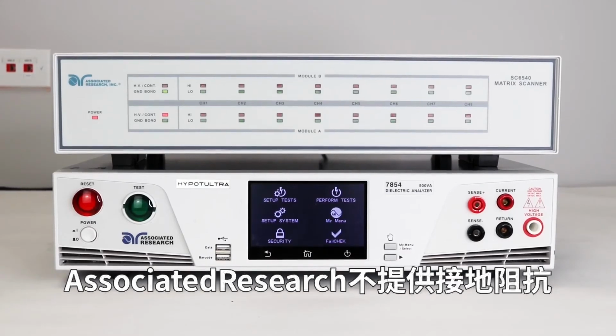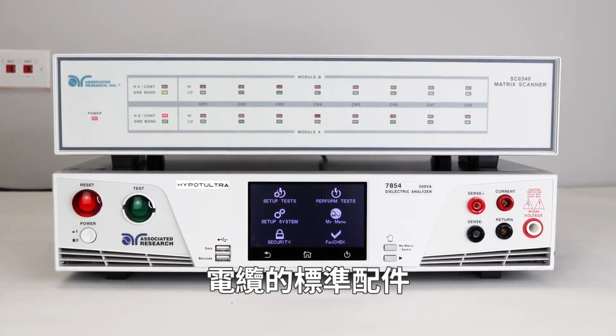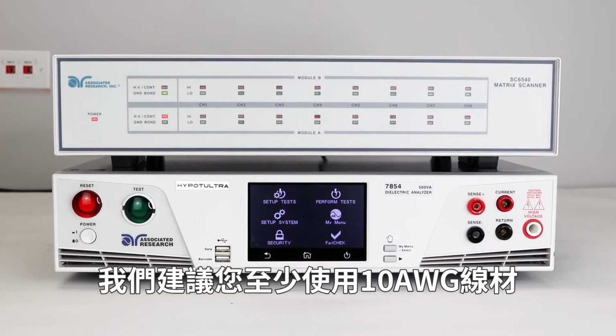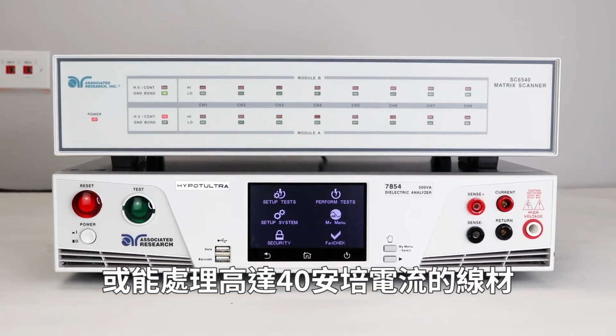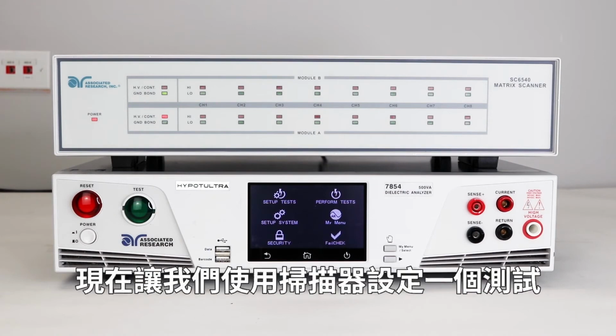Associated Research does not provide standard accessories for the ground bond channels. We recommend you use at least a 10 gauge wire or something that can handle up to 40 amps of current. Now, let's set up a test using the scanner.